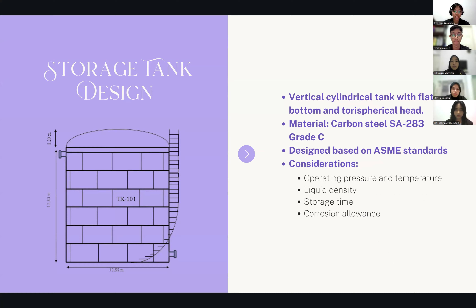The design of the tanks involves the following steps. A. Determining the tank capacity based on dimensional consideration, height, and diameter. B. Determining the design pressure according to the tank operating pressure. C. Calculating the shell and head thickness based on ASME standards, which is the maximum allowable stress value for common steels. Next.